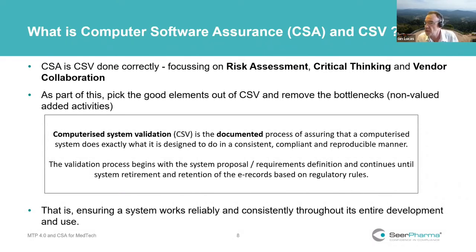So focus is on that and vendor collaboration. So we all work with vendors. The vendors do a lot of work, a lot of good work. If you're buying software, we spoke about Excel before. Think about any software that you use, what we should be doing is placing a lot more emphasis on the testing that the vendor has done so that we focus our work on the bits that we change, the configurations that we make, the customizations that we make, and we rely on the vendor's documentation to actually support that. And CSA is all about that.